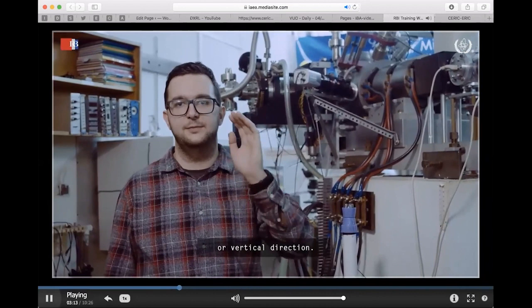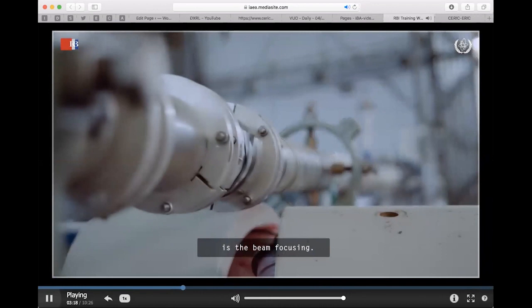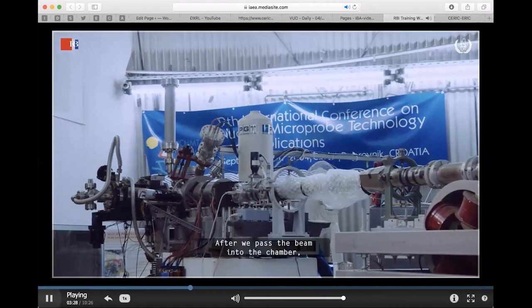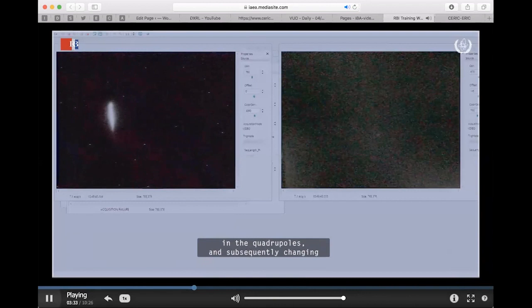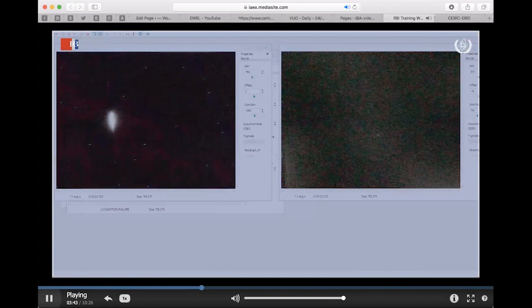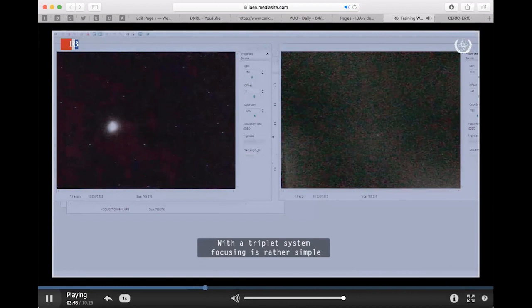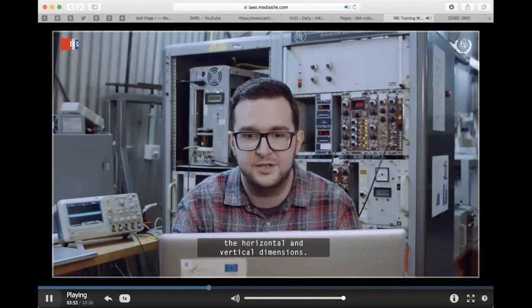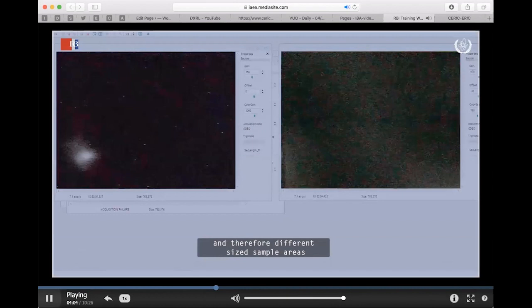The first step in the microprobe experiment is the focusing of the beam. To enable precise focusing with quadrupole magnetic fields, incoming ions have to travel along a well-defined trajectory. After passing the beam into the chamber, we focus the beam by changing the currents in the quadrupoles and subsequently their magnetic fields. With the triplet system, focusing is rather simple, as we can almost independently focus the horizontal and vertical dimensions. After the beam is focused, we can turn on the scanning coils controlled by the data acquisition system, and different sample areas can be investigated.